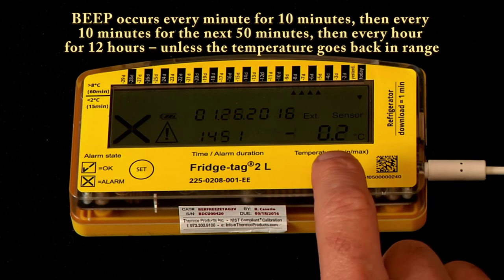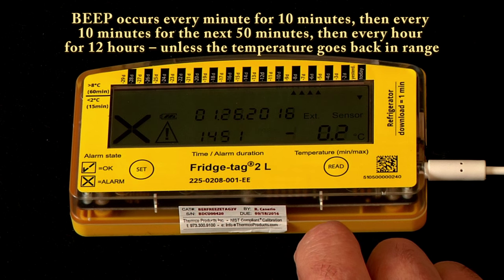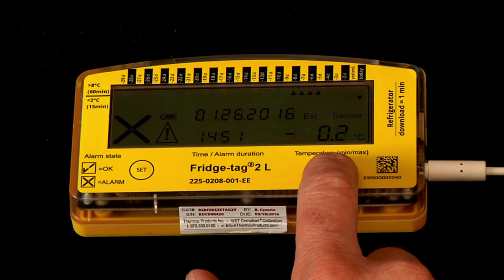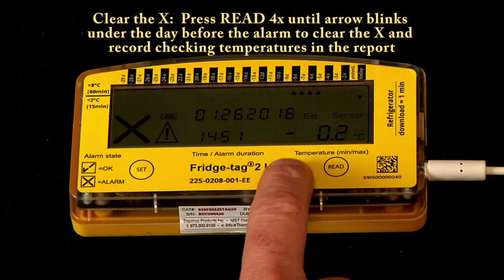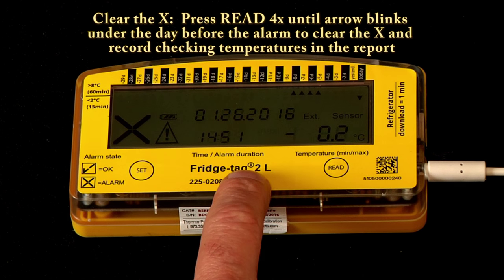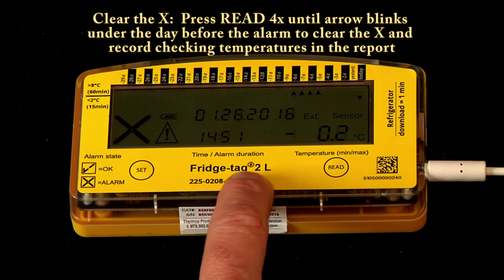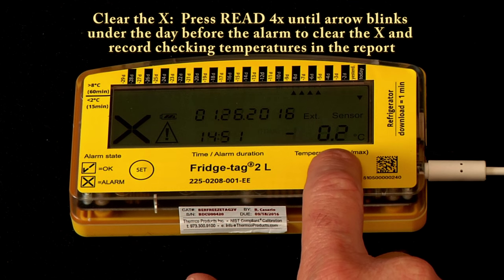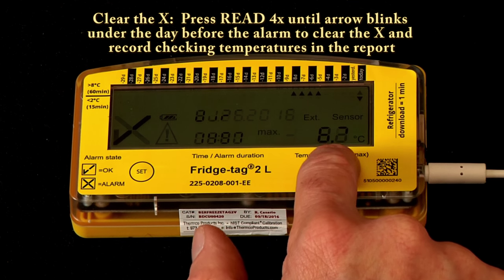So how do we clear the beep? First, fix the temperatures and make them correct in your storage unit. Next, press the read button to clear the alarms. The Fridge-tag 2L, and any FridgeTech sold after the fall of 2014, allows you to clear the X as well. Here's how: press the read button one time.